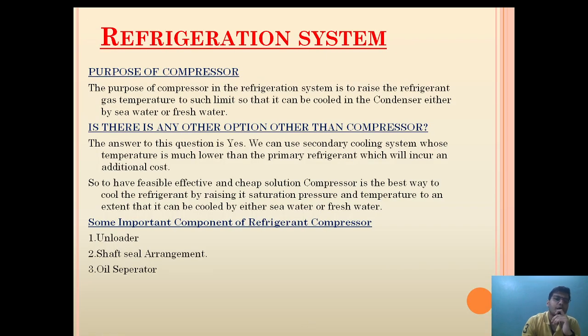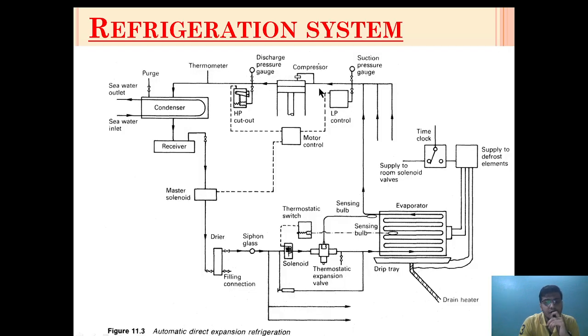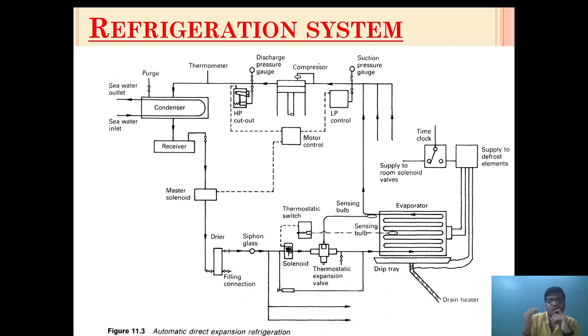Now let's see the main functions of the compressor — why the compressor is provided. The purpose of the compressor in the refrigeration system is to raise the refrigerant gas temperature to such a level that it can be cooled in the condenser either by sea water or fresh water. To make sure that the refrigerant saturation pressure and temperature can be raised to such a level that it can be cooled by the cheaply available sources such as sea water or fresh water — that is why the compressor is provided in a refrigeration system.